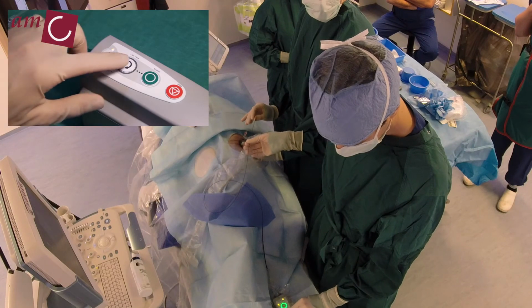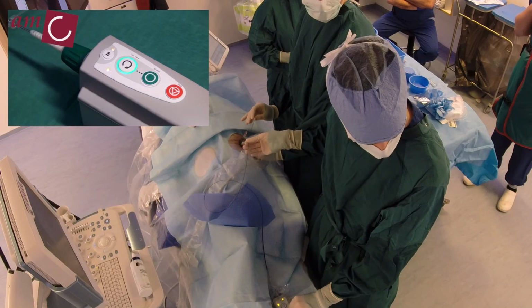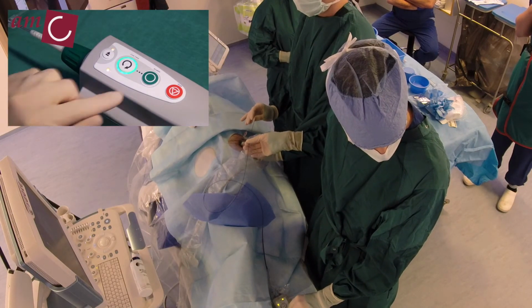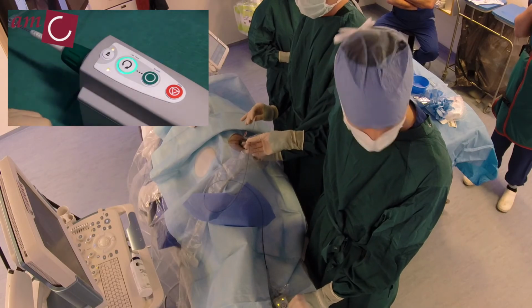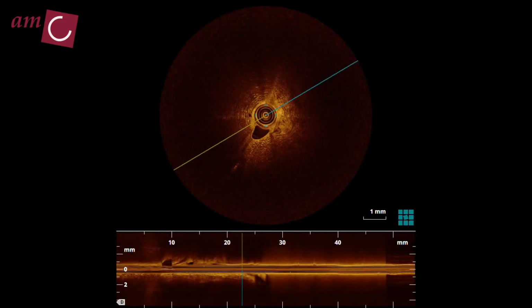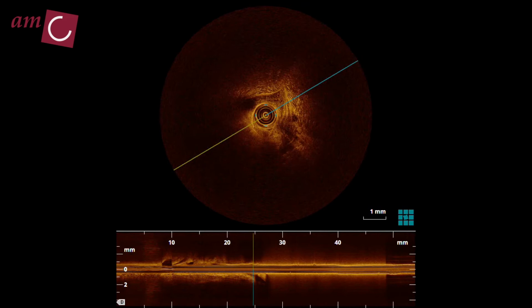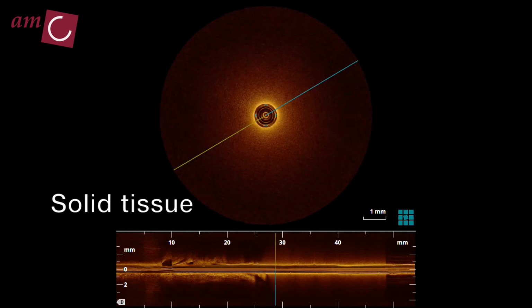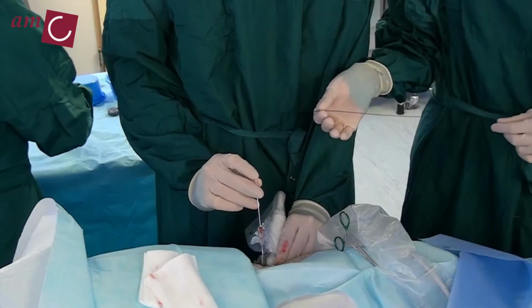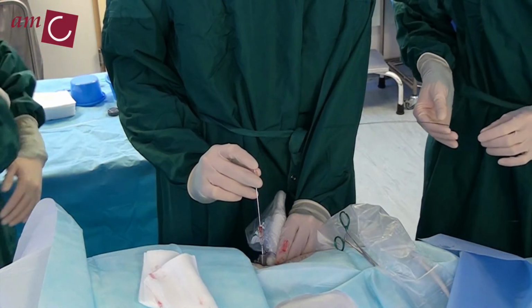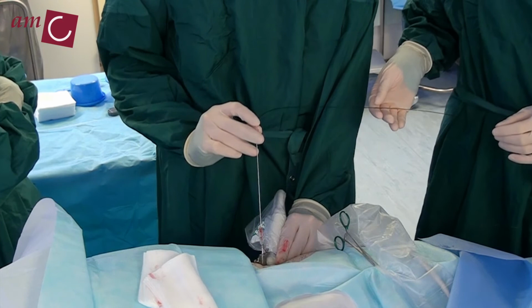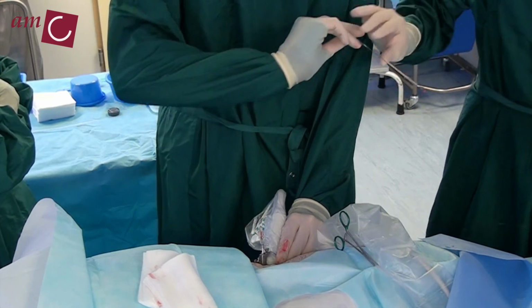Perform an OCT scan with the console set at 541 B scans per dataset. Check the scan for quality, artifacts, and the appearance of solid tissue. Repeat scanning until a minimum of 3 OCT datasets is acquired. Remove the OCT probe and trocar needle, leaving the introducer needle in place.